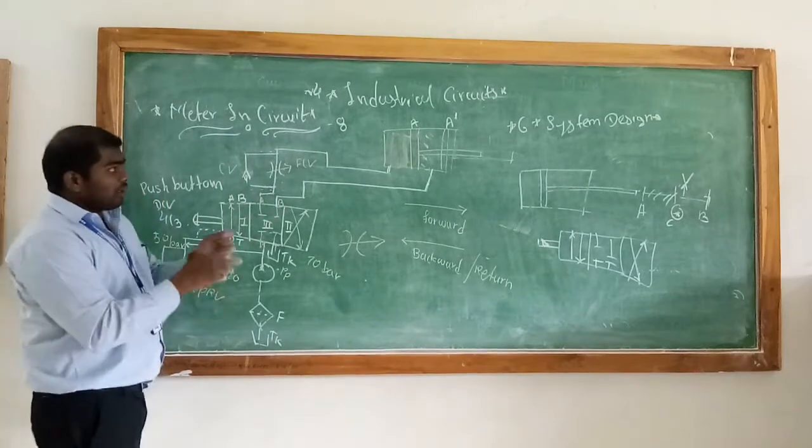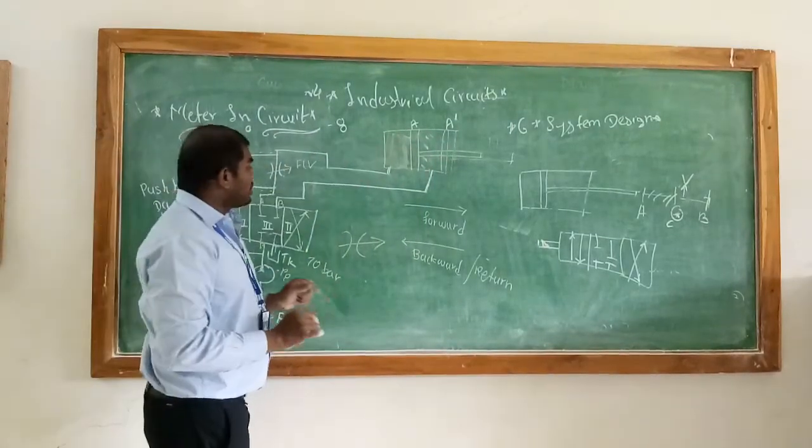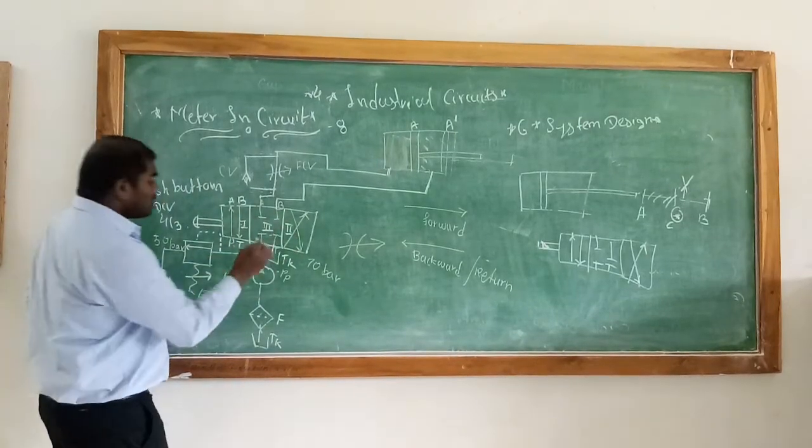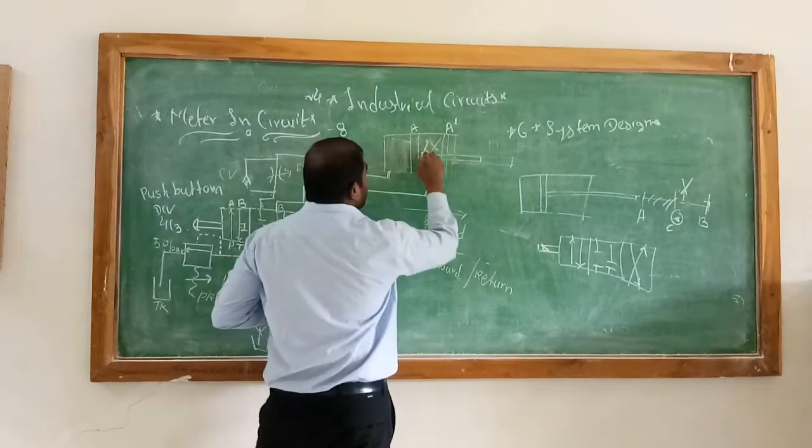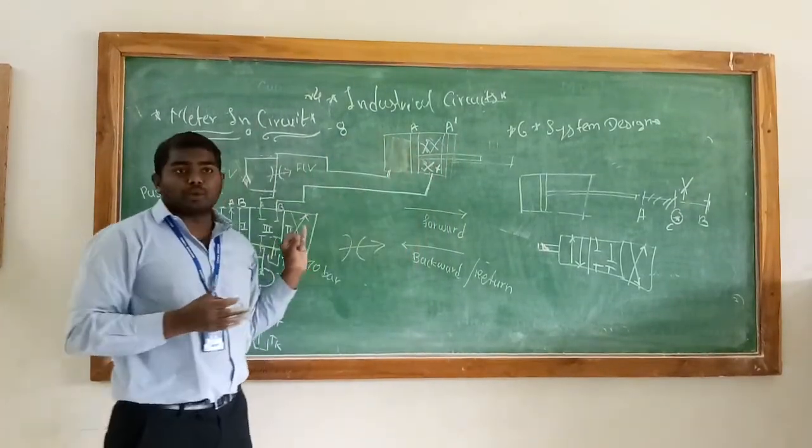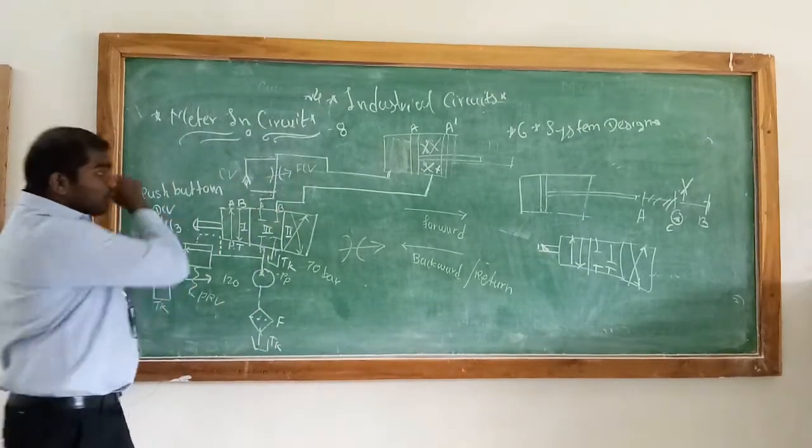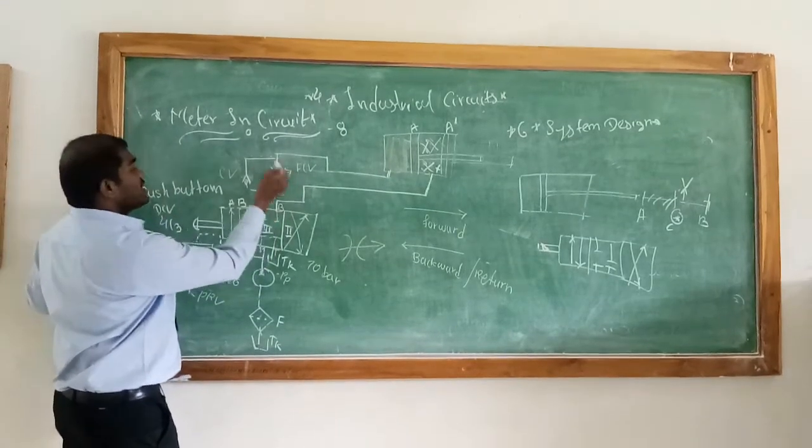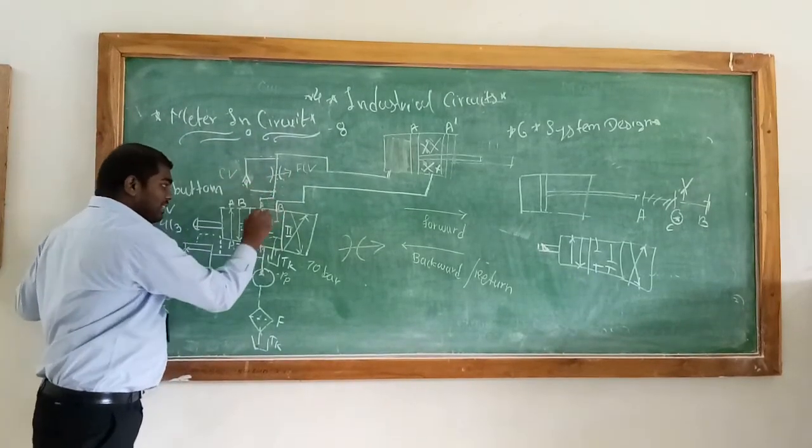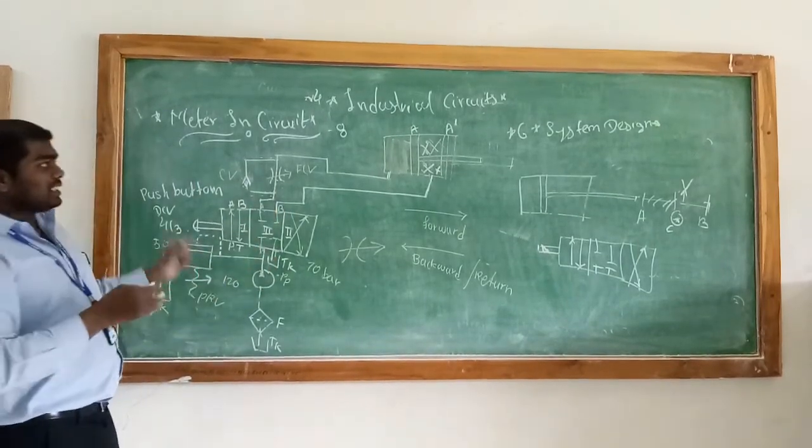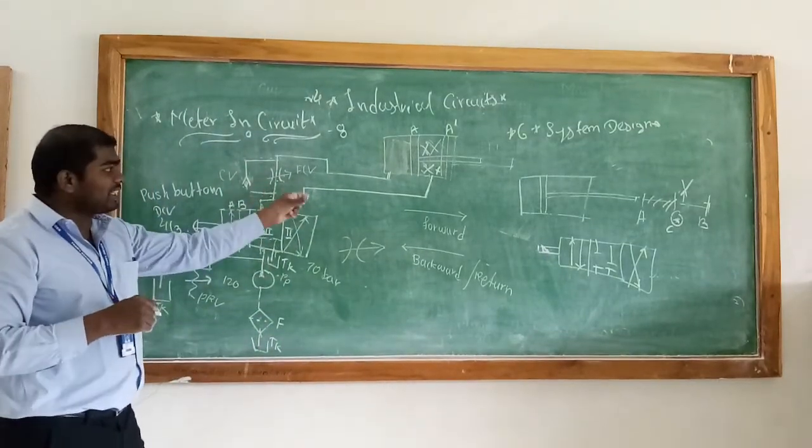So this portion will be filled up with the fluid. So the fluid has some energy. So it will be passing some pressure. So pressure will apply force above the area. So depending that much amount of pressure, it will get the magnitude of the force. So how much output you want, definitely that output will be easily gained. Now when it will cover this distance, this is just considered position A to C. Fluid which is present from the backward side, which is already present here, that fluid will try to go from this place. It will be connected to B. So that B will be connected to T. See here at this place, B is connected to T. So it will go to the tank and control the flow inside the cylinder. So this is for the meter-in. But after bringing your piston at position C, then you have to return this piston also. At that time, you have to change the position of DCV first to DCV second. So the fluid will flow from P to B. That fluid will come in this section and retract the piston to its original position. But similarly, we have some fluid here. The fluid will go from this place. It will also have flow from this section and this section also. But the resistance offered by the check valve is less as compared to the flow control valve. So the fluid will be moved from the check valve. And then again, it will be moved from A to T.